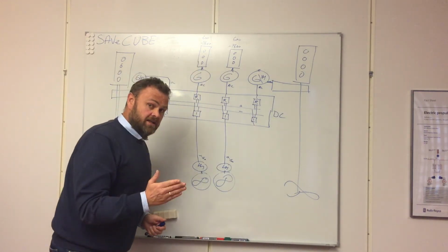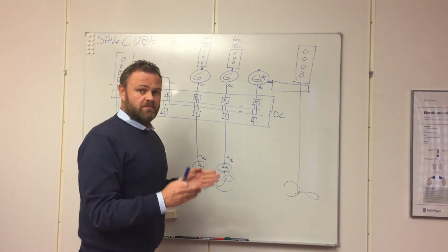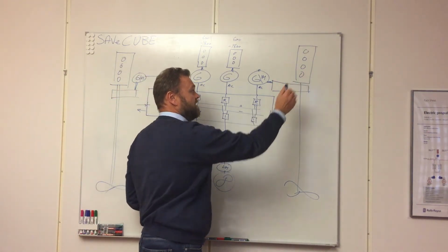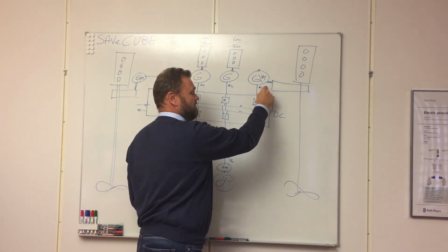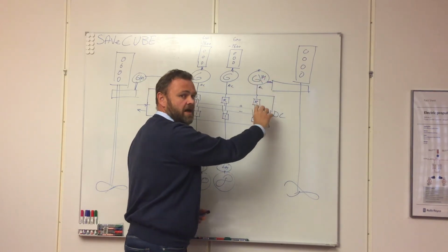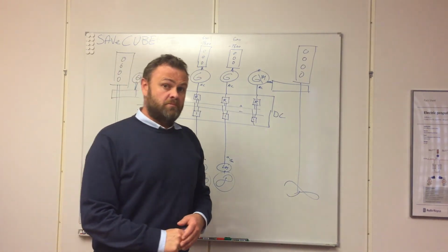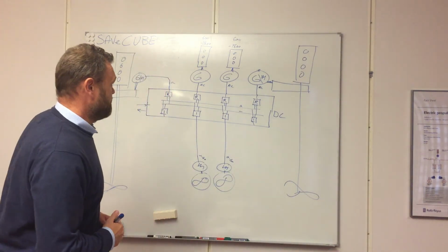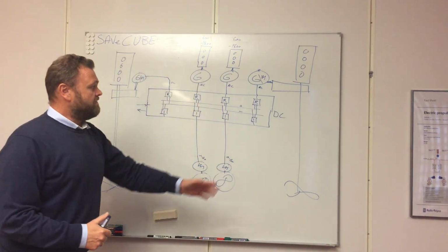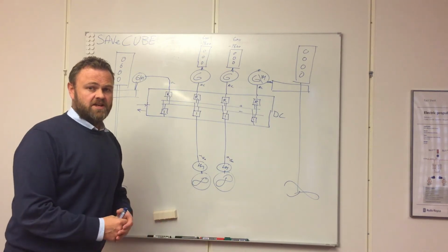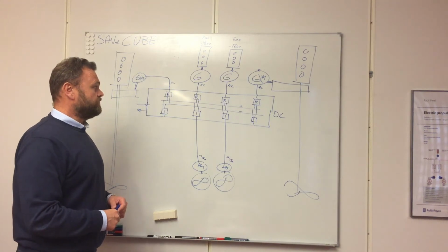And in addition, you still have the same functionality of variable speed of the main engine, because you do not have to produce fixed frequency from the generator due to the fact that you are connected to this DC bus inside the Save Cube. So with this, you have a Save Cube for a hybrid installation or for a full electric, as we discussed.